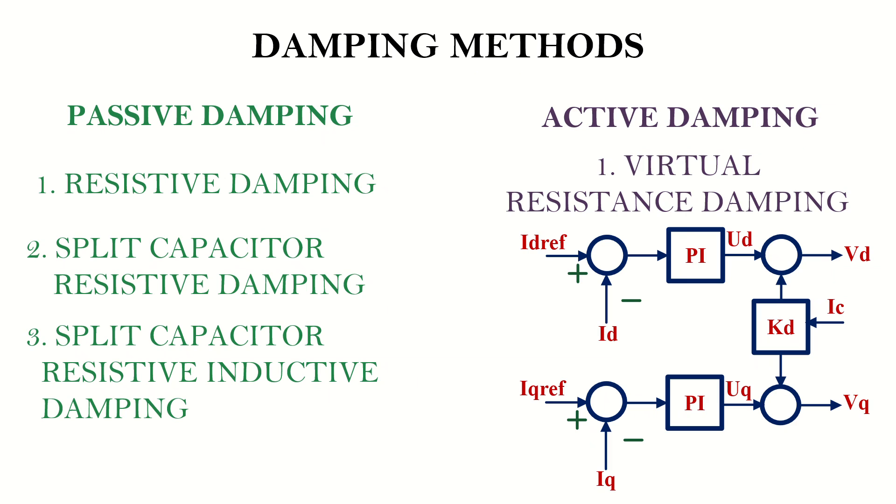This prevents the PWM converter from exciting the resonance of the LCL filter. This approach is equivalent to placing a resistor in series with the capacitor, resulting in similar performance without any additional loss in components.